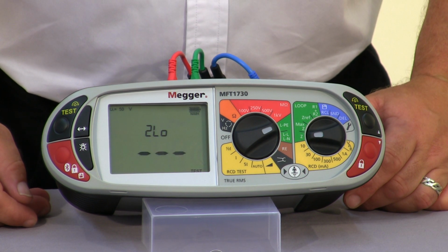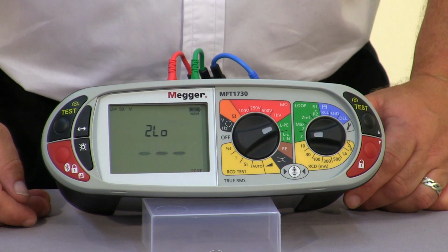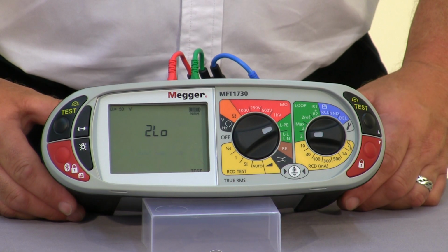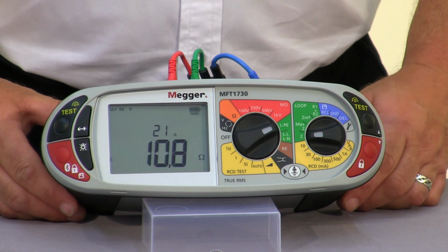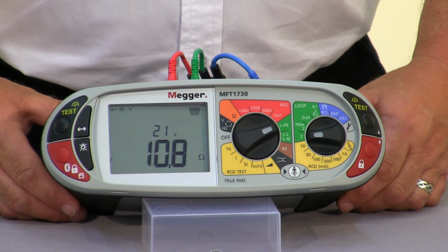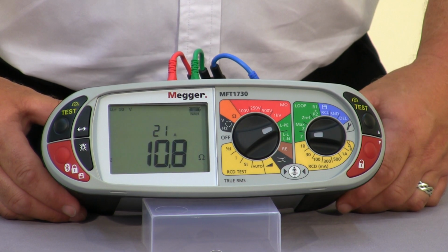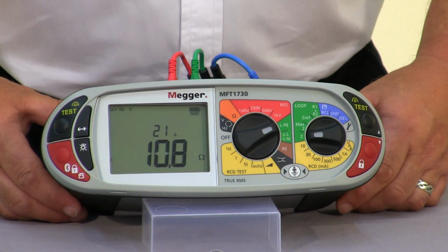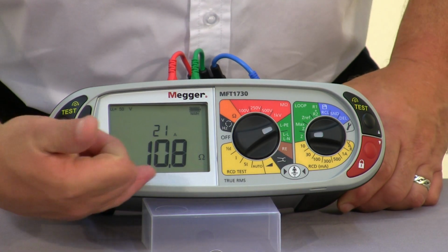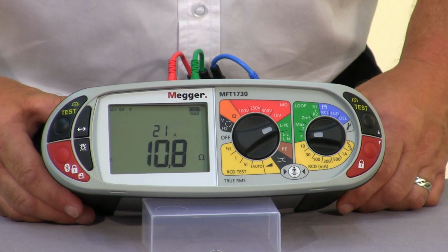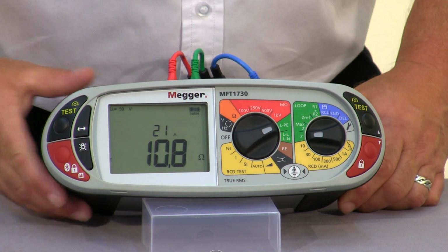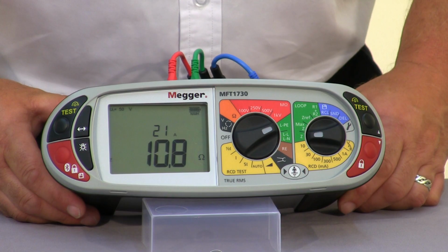Again, apply the mains voltage, and the unit, once it's seen the voltage there, audibly indicates that it will automatically start the test. Now the two-wire no-trip test is advantageous if you're looking to take a reading on a luminaire circuit, for example, where there's no neutral. So this gives you the facility to actually carry out the test from the light switch. And again, the reading displayed, we've got 10.8 ohms and a PFC value on the second parameter of 21 amps.